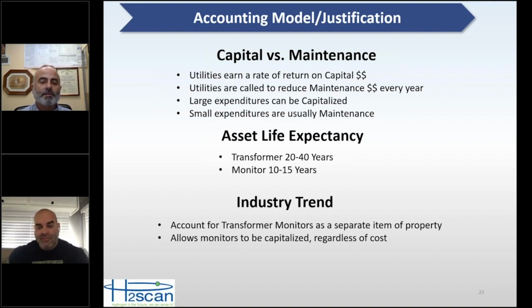The other issue is that the typical life expectancy of a transformer is 20 to 40 years, and your monitors only generally last about 10 to 15 years. So there's another mismatch there. Even if you put a monitor on a transformer when it's new, you're going to have to replace that monitor 2 or 3 times in the transformer's life.